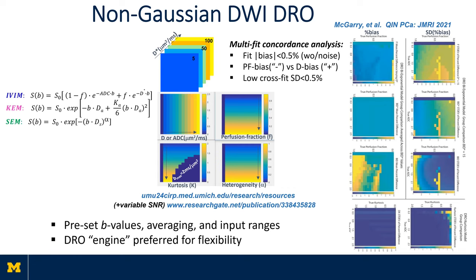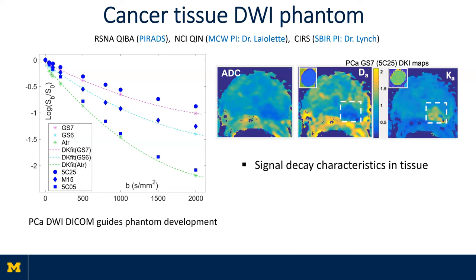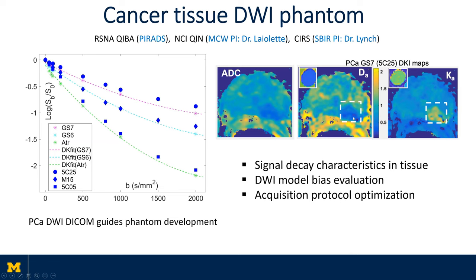We note that the developed diffusion imaging DROs use a preset set of B-values and input ranges, so sharing the actual DRO engines, as shown by previous speakers, would allow higher flexibility. Acquired patient images may also serve as DROs — for example, for acquisition protocol optimization such as reduction of the number of B-values required for the same fidelity of the fit, and also for development of tissue-mimicking phantoms. We used data shared by the Medical College of Wisconsin to design materials that imitate restricted diffusion in aggressive and indolent prostate cancer. The developed phantom can be used for evaluation of different biophysical models and their biases, and acquisition protocol optimization.